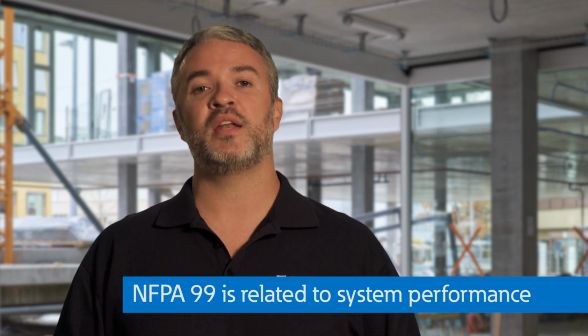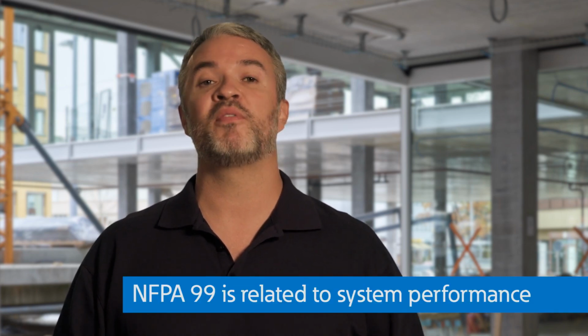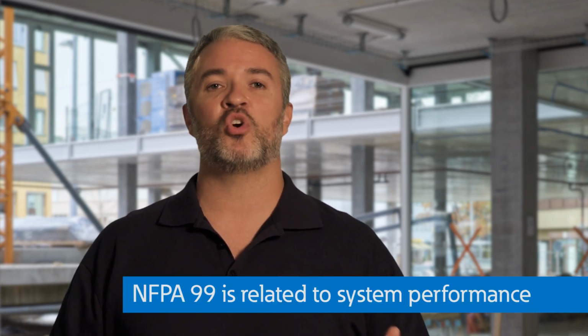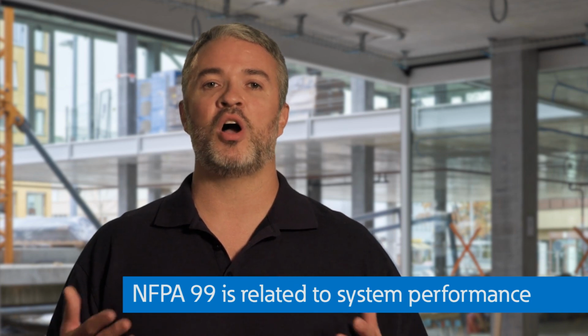As opposed to NFPA 70, which addresses installation requirements, NFPA 99 addresses issues around system performance. Many of the requirements of NFPA 99 are often extracted and included in the NEC to make it easier for the user. With respect to the essential electrical system, NFPA 99 addresses critical facility power distribution requirements for a wide range of equipment, lighting, and receptacles specific to healthcare.